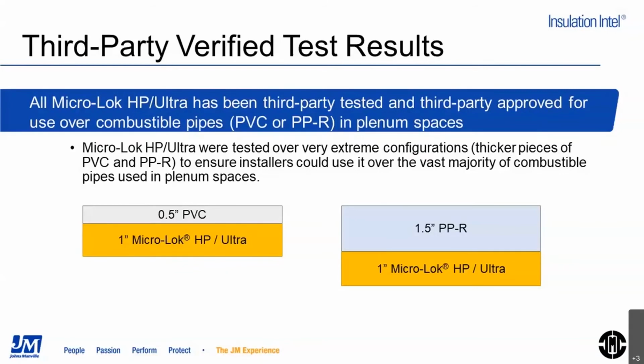And I also want to point out that Johns Manville manufactures Micro-Lok HP and Micro-Lok HP Ultra in 1/2 inch wall thickness as well. If you're using it in a Plenum, the wall thickness has to be 1 inch or thicker because that's what was tested here. So even though we do sell 1/2 inch, that will not be good enough for the Plenum space because that's not what we have listed. If you need to install thicker Micro-Lok HP or Micro-Lok HP Ultra, that's not a problem. You just cannot go less than 1 inch, and that's very important to note.